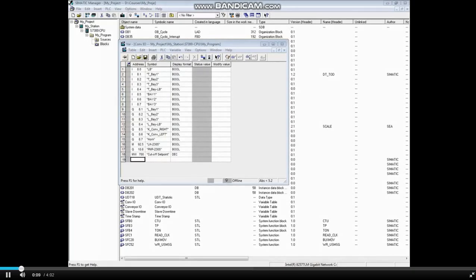The permanent modify function sends out the user supplied modified value every scan, at the beginning of the scan, or the end of the scan, depending on the settings you make. You can also choose to send the modify value out when the CPU goes to stop. With a variable table open, turn on monitoring.